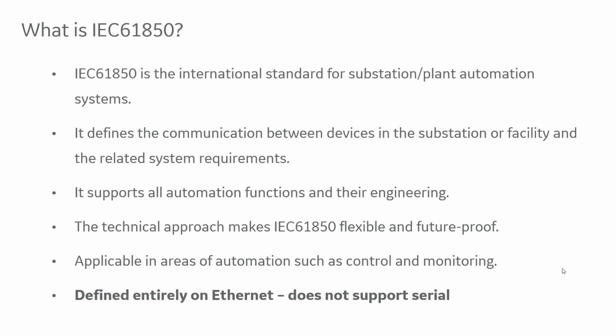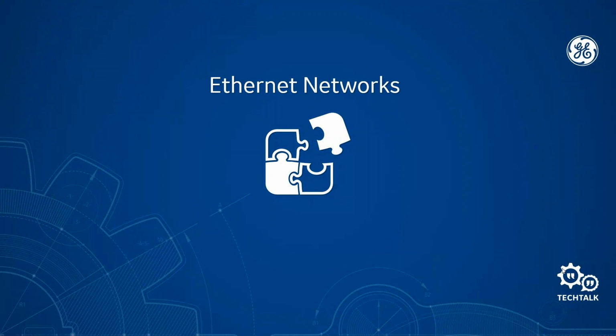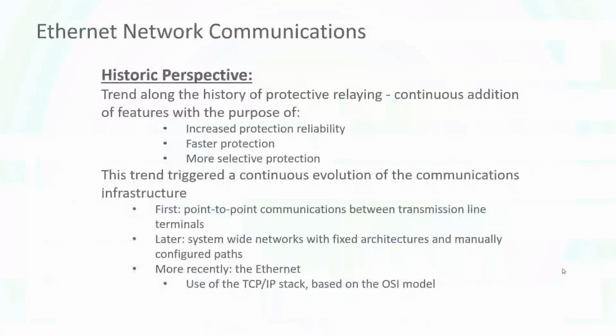Before we get into more details of 61850, let's talk about Ethernet networks, since 61850 is designed for that. We need to know what Ethernet networks are and be able to identify, create, and design them, so we can support whether it's Modbus over Ethernet, DNP over Ethernet, or 61850. I don't say 61850 over Ethernet, because by definition 61850 is over Ethernet.